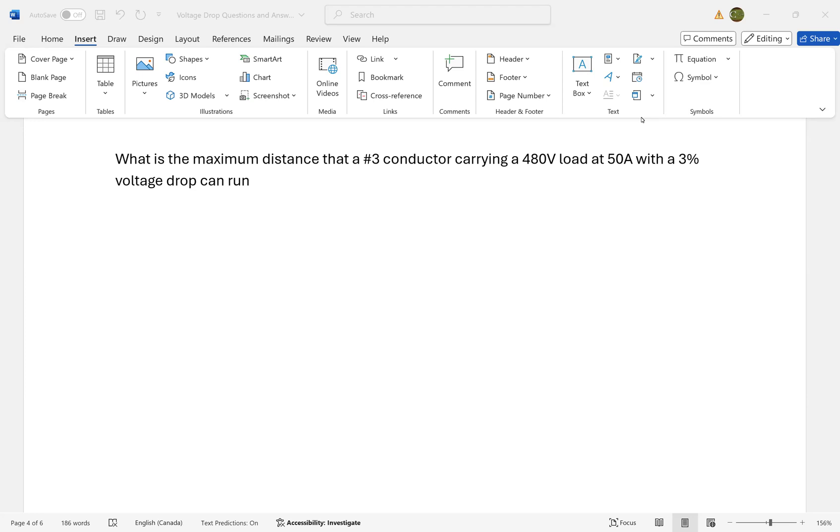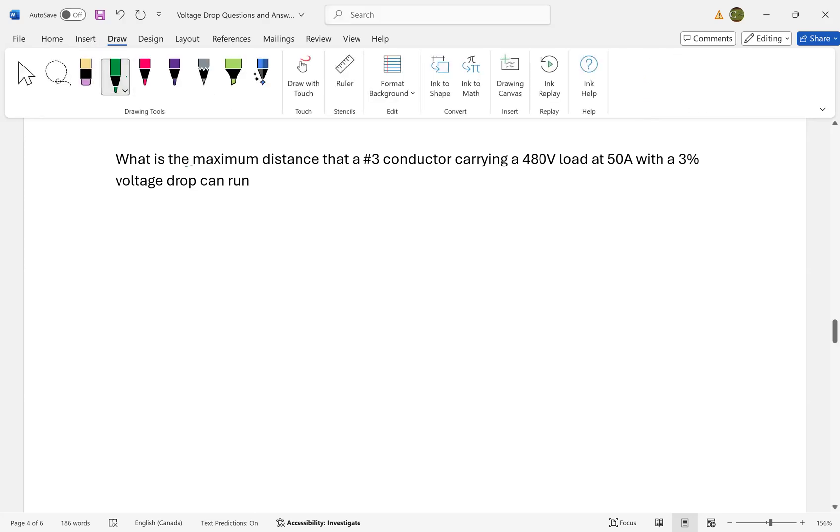Here's a voltage drop problem asking: what is the maximum distance that a #3 conductor carrying 480 volts at a load of 50 amps can run if we can accept a 3% voltage drop?